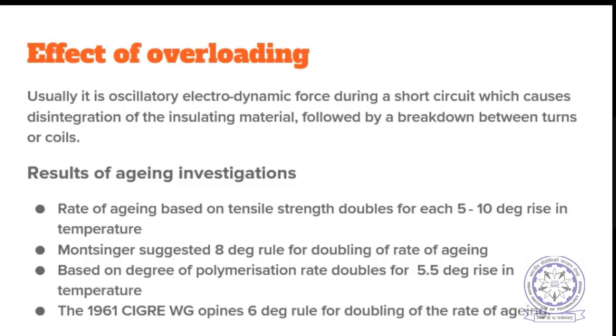Now, results of aging investigations. Yesterday we have seen the rate of aging based on tensile strength. If we go by the tensile strength test, it is reported that the rate of aging doubles for every 5 to 10 degrees centigrade rise in the temperature. But as per Montsinger, a scientist, he suggested the 8-degree rule. So for every 8 degrees, the rate of aging will double. That is his rule.